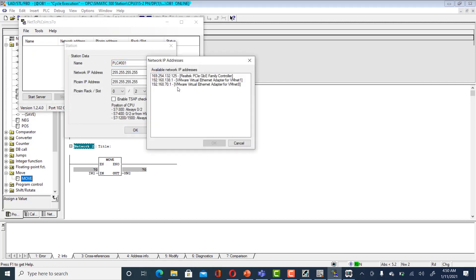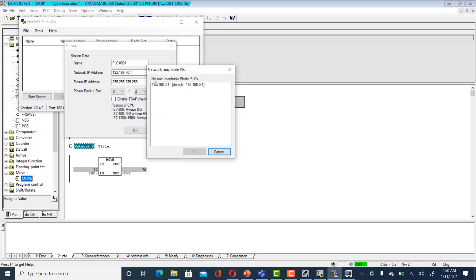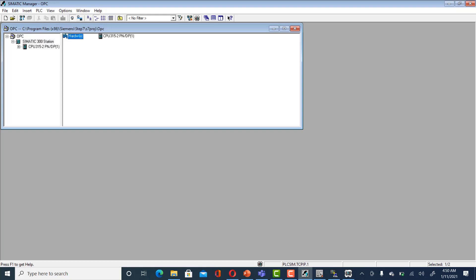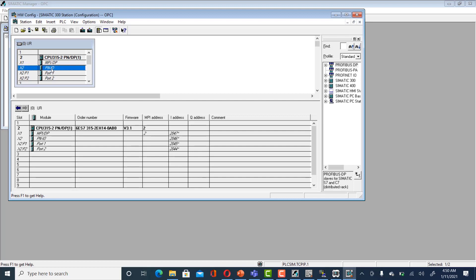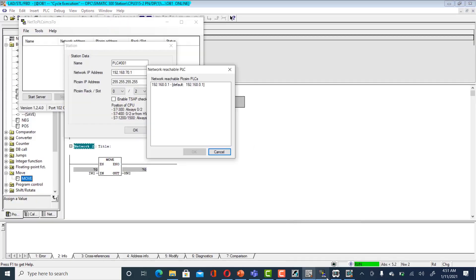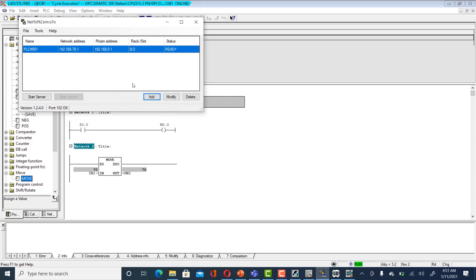Select the network adapter IP of your system — for example, 192.168.70.1. The PLC Sim address is 192.168.0.1. To find it, go to hardware in Simatic Manager, click on the CPU, and you will see the IP address, e.g. 192.168.0.1. Select that IP address, click OK, and start the server. Now it's running. Next, go to the Kepware server.